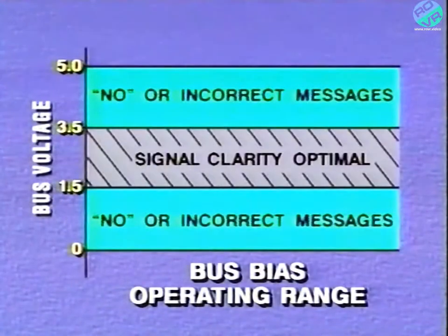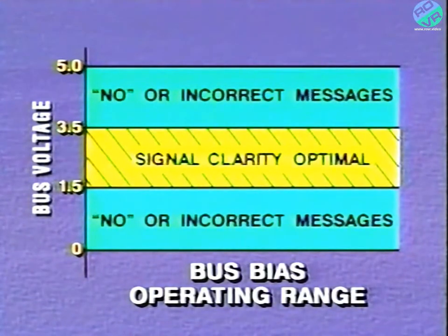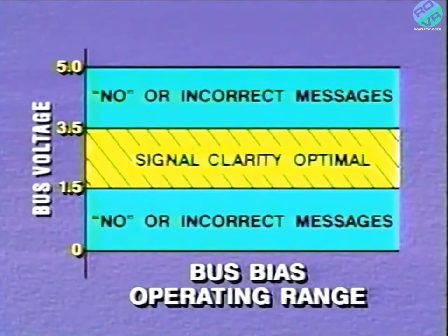While we're on the subject of the voltage required to operate the bus, the minimum bus bias operating voltage is 1.5 volts, and the maximum operating voltage is 3.5 volts. Inside this range is where signal clarity is optimal. If voltage goes outside this range, the controllers will have difficulty interpreting the message.